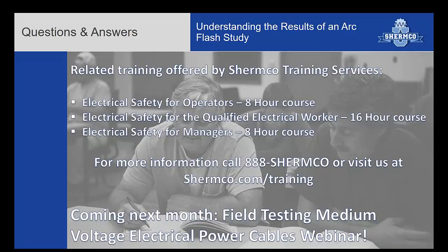I would highly recommend that we just go ahead and TDR every new cable installed during testing, and then if you're doing maintenance, once again, whatever data you collect and put into the study, garbage in, garbage out. So the better you can make that data, and the more during maintenance that you're collecting that data, maybe you had a study and you're saying, well, I don't really need to collect all that data right now. I would continually collect the data so that when the updates come up, the better that model is, you can see small changes, how it affected it. That's why they use those two methods.